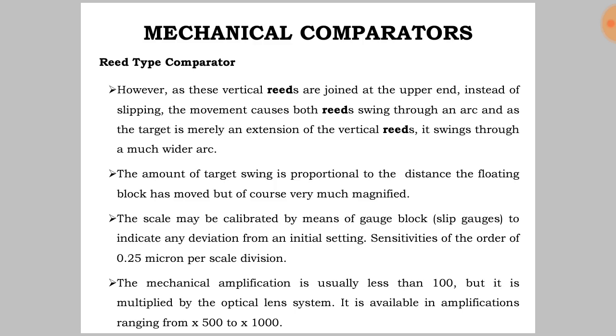Sensitivities of the order of 0.25 micron per scale division are achievable. The mechanical amplification is usually less than 100, but it is multiplied by the optical lens system, and it is available in amplification ranging from 500 to 1000.